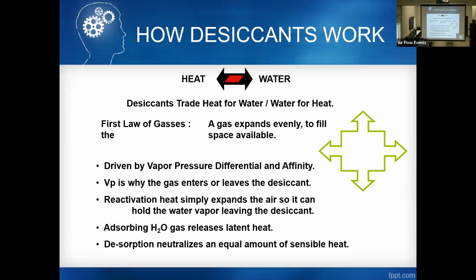Basically what we're doing is we're trading heat for water and water for heat. Again, we're dealing with vapor pressure. This is how we're removing the moisture as the desiccant rotates.